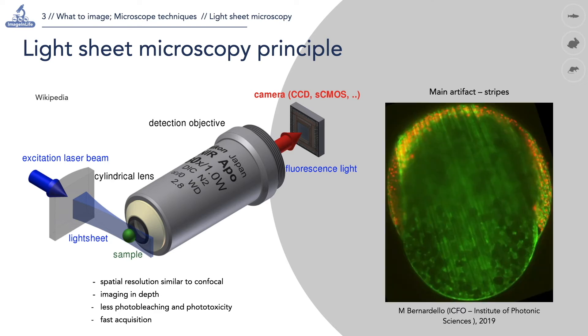The light sheet microscopy architecture brings an imaging artifact in the form of dark stripes. They happen because of the absorption of light by dense objects on the light path.